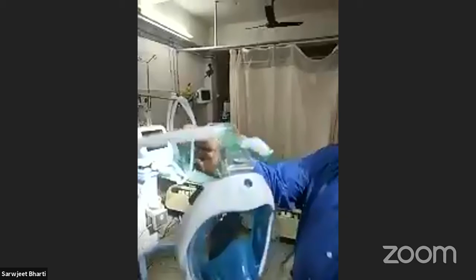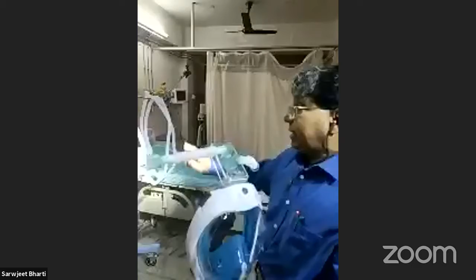The connectors, essentially, we have made two types. We have one with double port and the other one with single port. The double port is whenever we use any oxygen device which is not a ventilator, in which case we have to use this. To the other end, we have to attach a filter, and you have to attach a variable mechanical filter. If this is a mechanical filter, you can increase or reduce the pressure, which gives what is called CPAP. But in CPAP, actually this is a PEEP valve, but by definition CPAP is PEEP applied during spontaneous respiration. So this is the second connector that we have made.